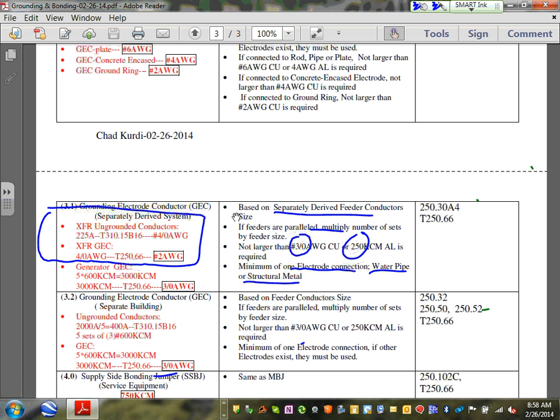So 225 amp, guys, take it to 310.15(B)(16). You get yourself 4-aught. Can you guys see that? It's 4-aught that you got. From the 4-aught, take this one to 250.66, and your grounding electrode conductor size is number 2. Exactly like the supply side bonding jumper and the system bonding jumper. They're identical to a limit. When you start exceeding 1100 kcmil, they start getting different. So it's identical, gentlemen, to the supply side bonding jumper and the system bonding jumper.